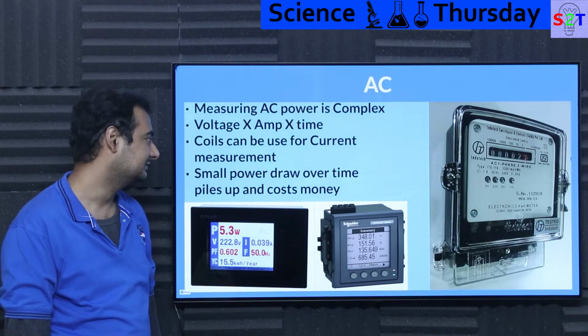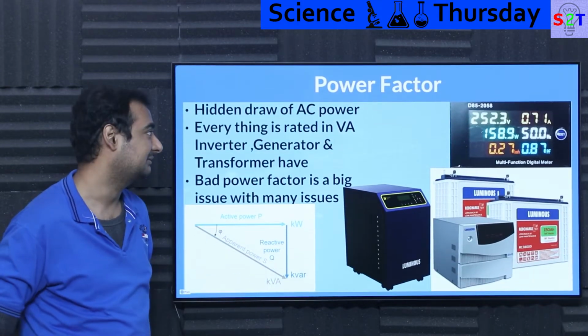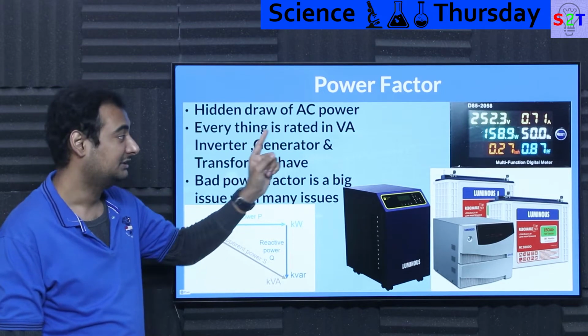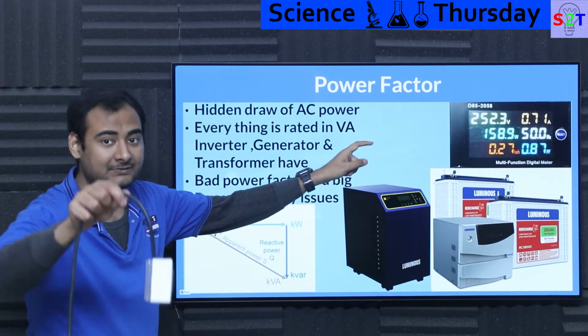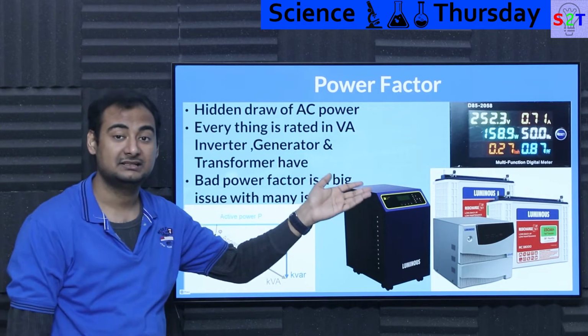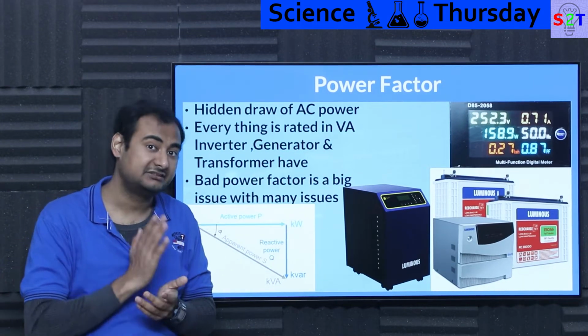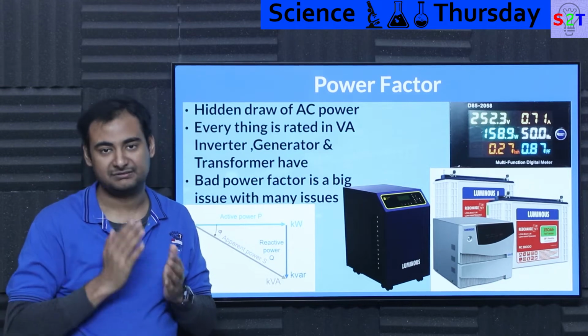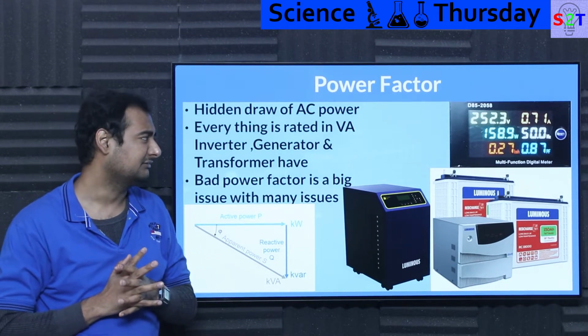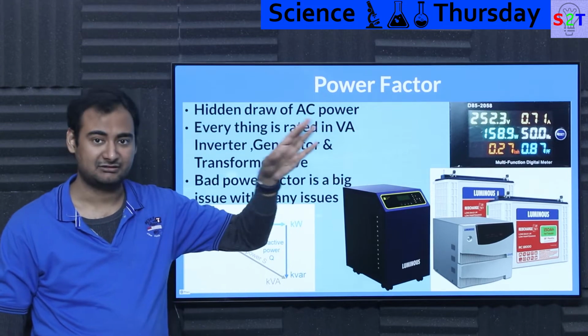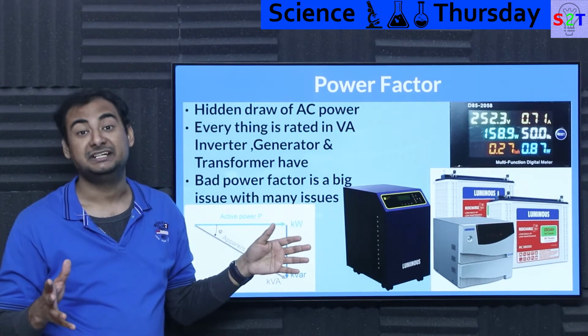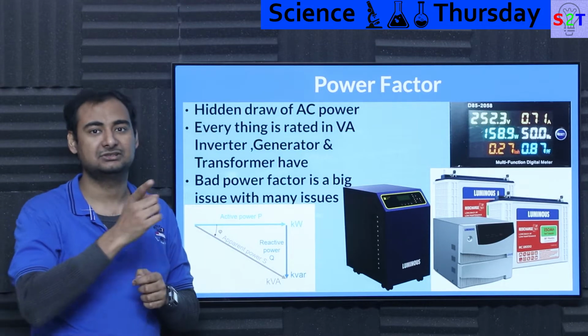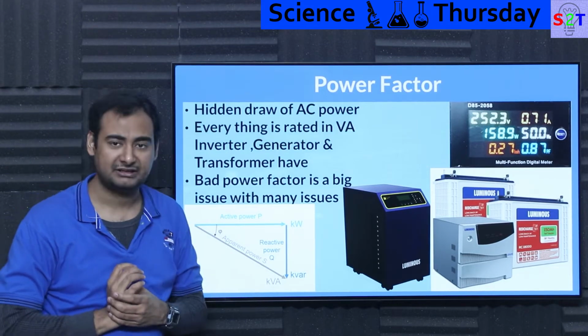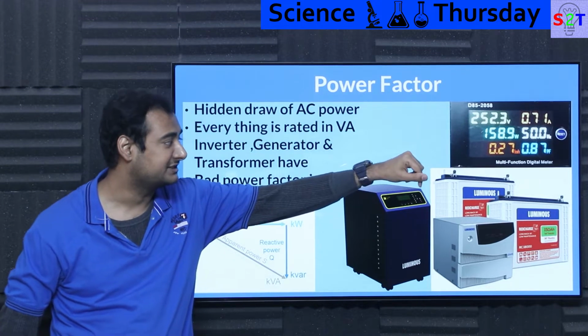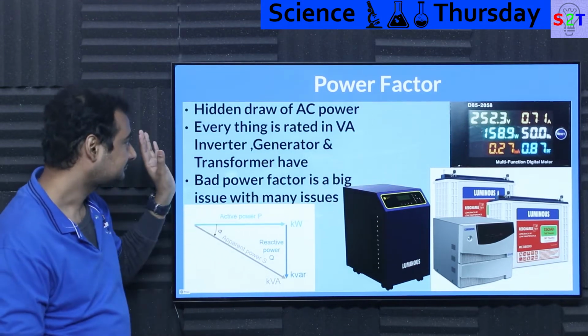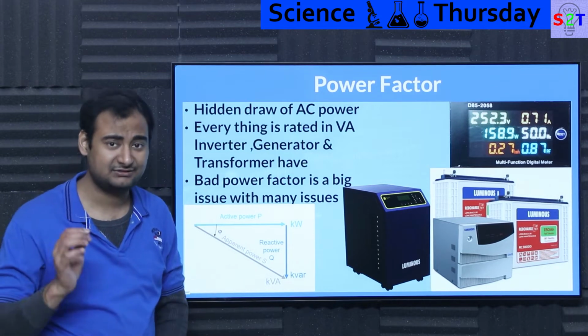AC power is a bit complicated, especially when you have to multiply by time. Now power factor is the most dangerous aspect. When I connected my meter to the UPS system, I realized the power factor was very fluctuating, because it has an active power factor correction system. At low power it was giving me dirty power, like 0.7 power factor when my UPS was only idling. But when it had high power draw, it started to go to almost 0.9, 0.85. Right now it's staying at 0.87, so it can easily sustain that kind of power load. This is the hidden power draw of an AC system.